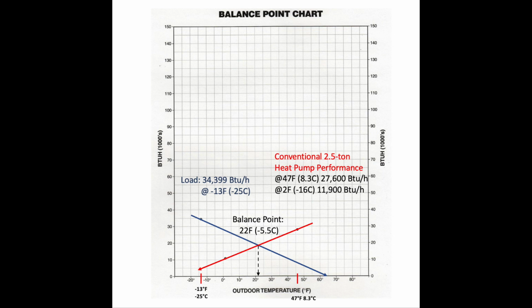The red line, in this case, is a conventional 2.5-ton heat pump that I plotted on the chart. The manufacturer told me at 47 or 8.3 Celsius, this unit would put out 27,600 BTUH. So I plotted that at 47. And the manufacturer said at 2 Fahrenheit or -16°C, it puts out 11,900 BTUH. So I drew a line that's called the equipment line. Where the equipment line crosses the load line, you drop an arrow down to the temperature grid and you see that the balance point is 22 degrees Fahrenheit or -5 Celsius.